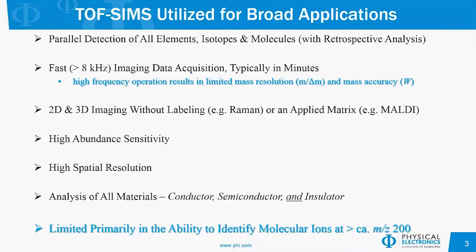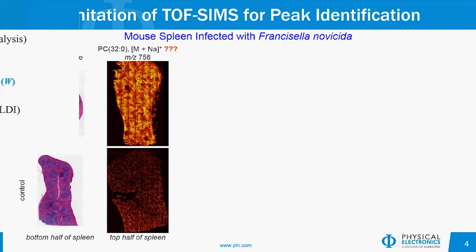Along with the speed inherent with TOF-SIMS imaging, because we're operating at a very high repetition rate, that has an impact on the mass resolution as well as the mass accuracy — two things quite necessary for identification of peaks in the mass spectrum. So one of the biggest disadvantages of TOF-SIMS is the ability to identify molecules that have a mass larger than 200 Daltons.